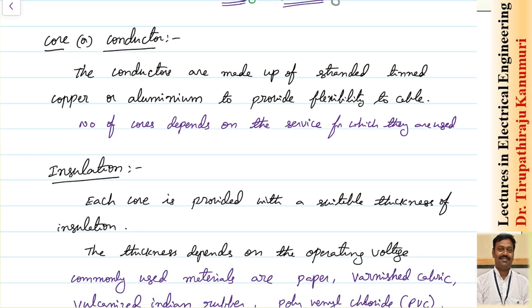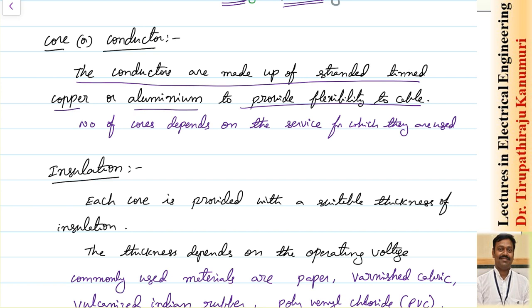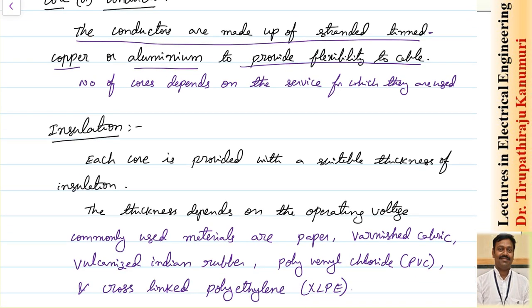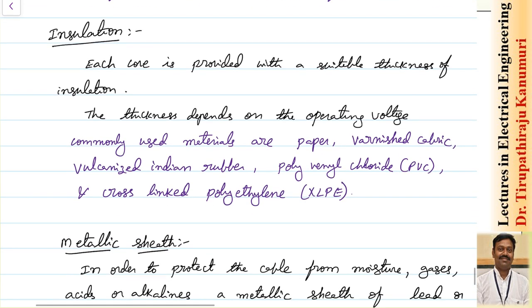The core or conductor is made of stranded tinned copper or aluminium to provide flexibility, since stranded conductors are more flexible during laying. Tin is applied over the copper to prevent interaction with the surrounding insulating material. The number of cores depends on the service — single core, two core, three core, or four core cables are available depending on the application.